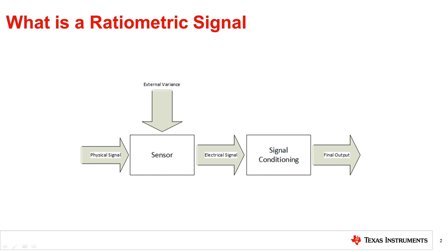In a ratiometric measurement, the conditioning of the signal is done with respect to the external variances as a reference signal instead of an absolute source. This means that the signal of interest is measured with respect to another signal to which it is proportionally correlated. Using ratiometric measurements, it changes from being an independent voltage or current to a component with much tighter tolerances. A simple example of this is a resistor.